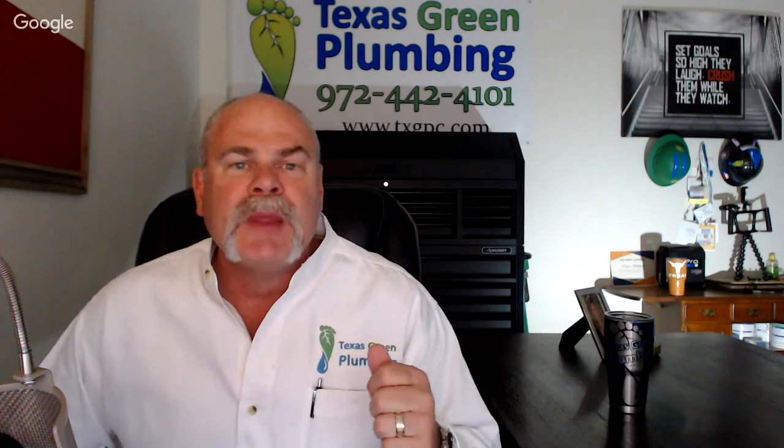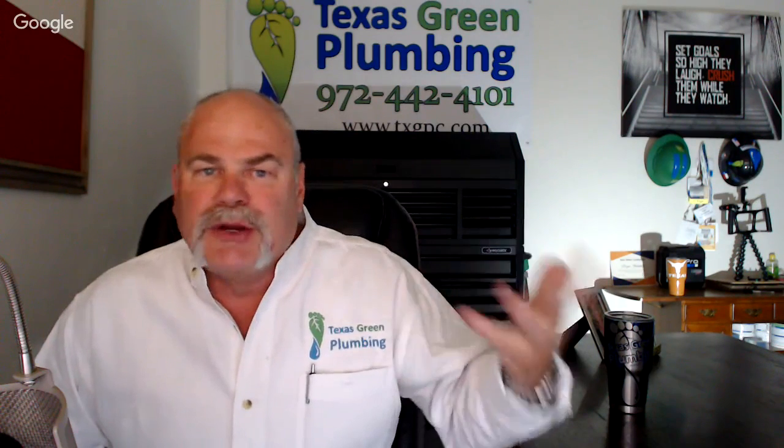Chances are probably yes. Unless you go with a very low BTU tankless water heater, you're probably going to have to upsize or increase the volume of your gas system. One thing a plumber should do before he ever starts installing a tankless water heater for you is to do a gas load calculation. The plumber will need to come into your house, get up in your attic or wherever your gas lines are run, measure every linear foot of gas pipe that you have, draw this out, and put the BTU rating for every appliance or fixture on there to make sure it's going to be big enough.